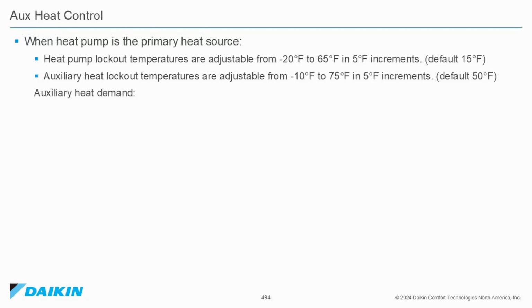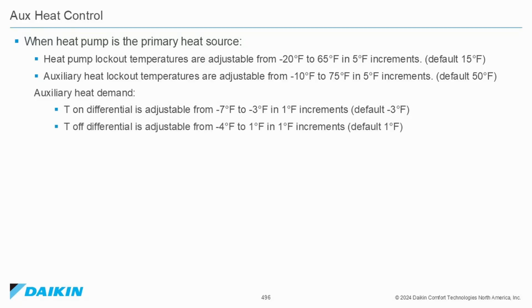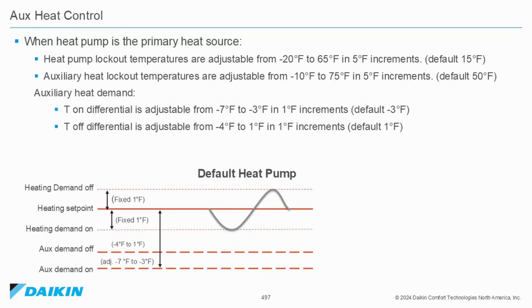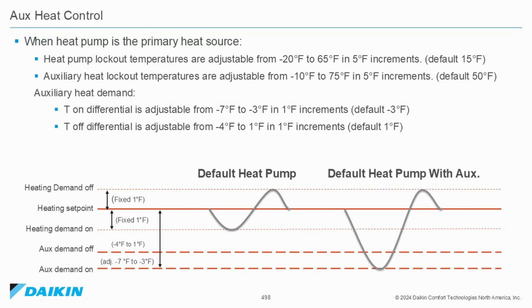Auxiliary heat demand. T-on differential is adjustable from -7 Fahrenheit to -3 Fahrenheit in 1-degree increments. Default, -3 degrees Fahrenheit. T-off differential is adjustable from -4 degrees Fahrenheit to 1 degree Fahrenheit in 1 degree Fahrenheit increments. Default setting, 1 degree Fahrenheit. This graph showing the set point, default heat pump settings, heat off demand to heat on demand, and default heat pump with auxiliary, showing the auxiliary demand off and auxiliary demand on settings.